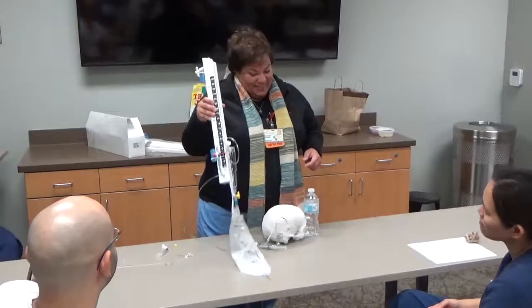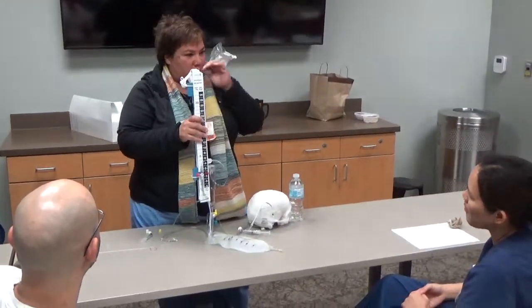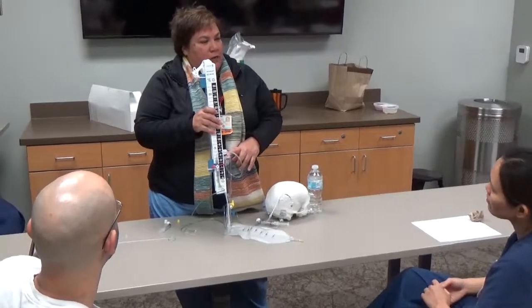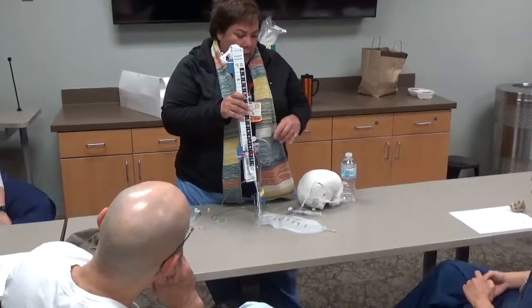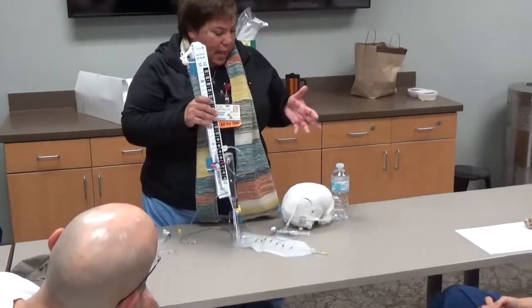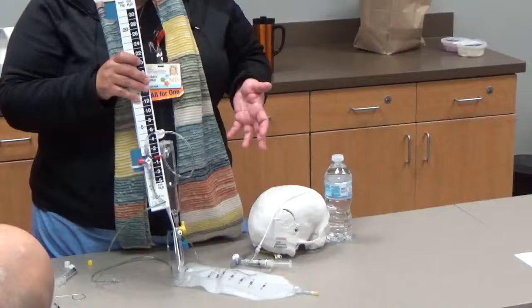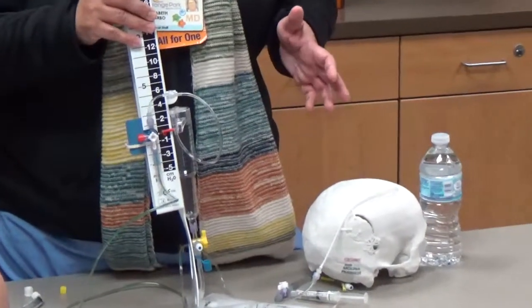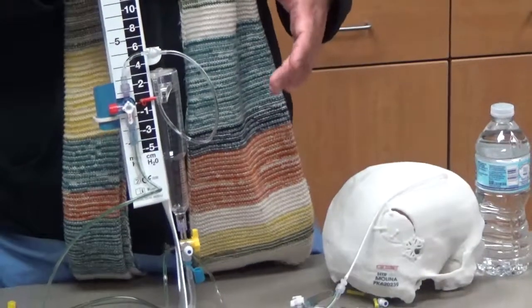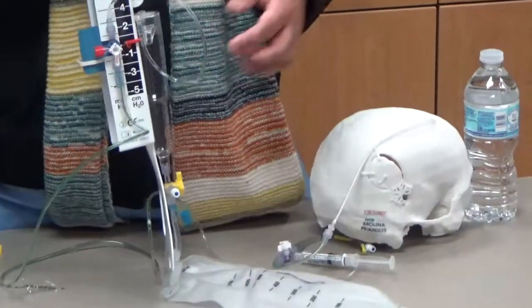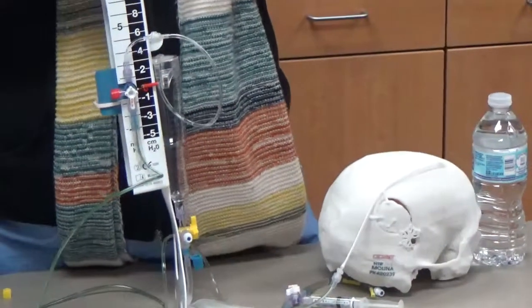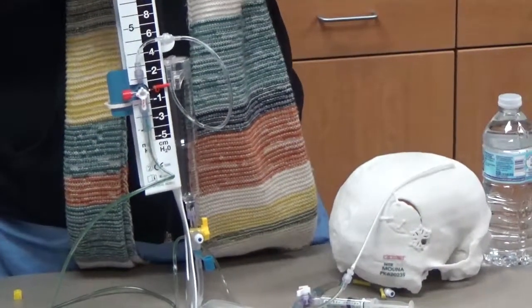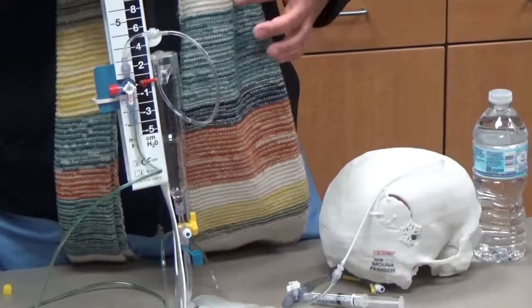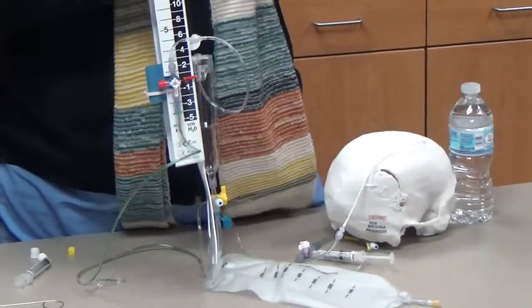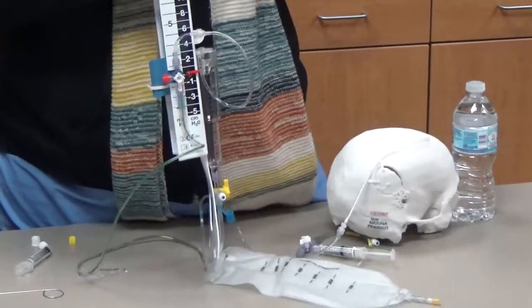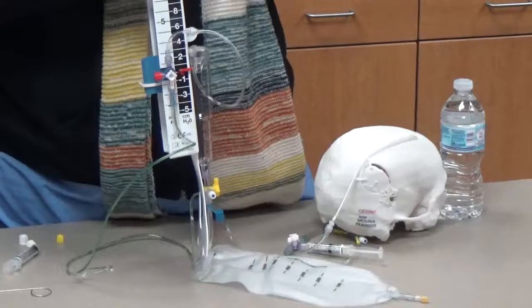So it should always work. Now, there are times where it doesn't work, so why wouldn't it work? It might not work if you have a wet air filter. Certainly not going to work if you're not actually at the proper level, which is an issue we could talk a little bit more about, especially with the squirmy patients. Okay, and it's not going to work sometimes if you have air bubbles, like there's a little air bubble here. Sometimes you'll see a dampening of the waveform, so sometimes you will just have to reopen everything, allow a little bit more drainage to occur, to make sure you have a continuous fluid column and there's no air bubbles.